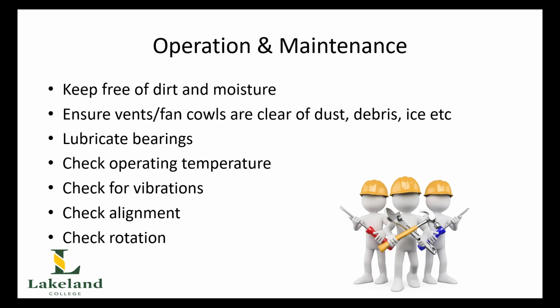Lubricating the bearings is normally a job left up to the electrician. They generally don't trust us with this because it's very easy to over lubricate a bearing. And you'll be talking about how much lubricant to put into a bearing later in your 4th class studies. Next is to check operating temperatures. We often do this going around with a simple pyrometer, where you gun the bearings and just make sure that they are not overheating. If they are overheating, then we might, for example, need to increase the cooling water, if there is one, the cooling oil, if there is some, or even something like the fan itself. But we need to check the temperatures of these things to make sure they're not overheating, which means they would go down on over temperatures.